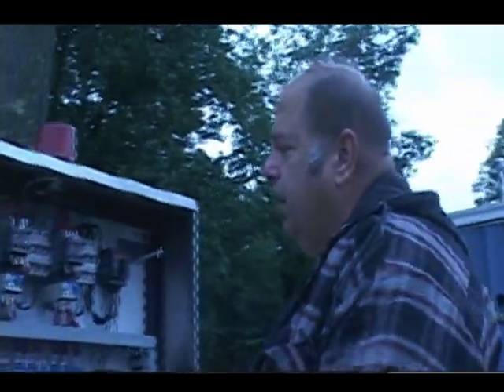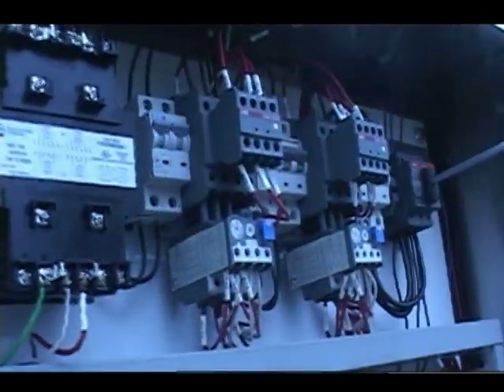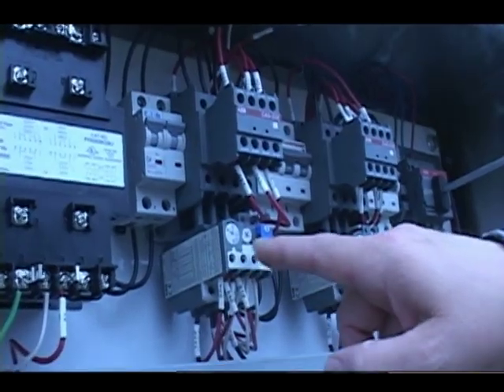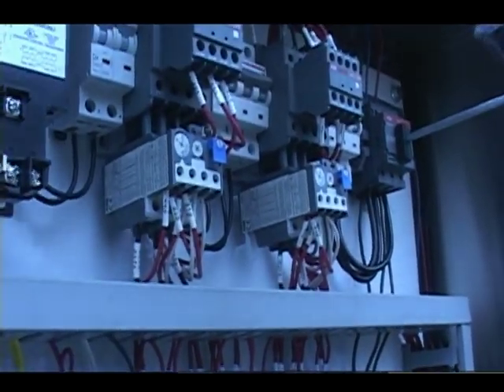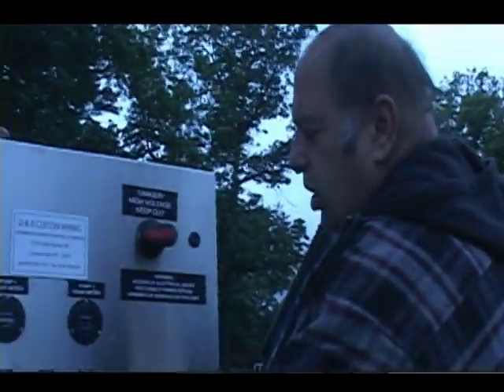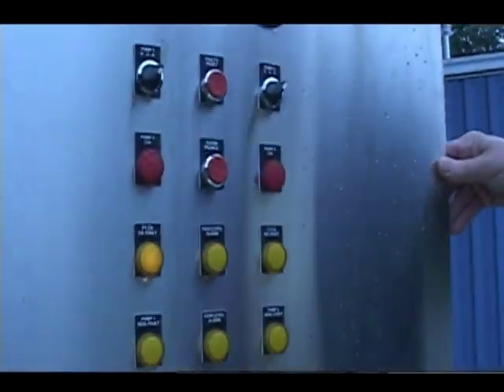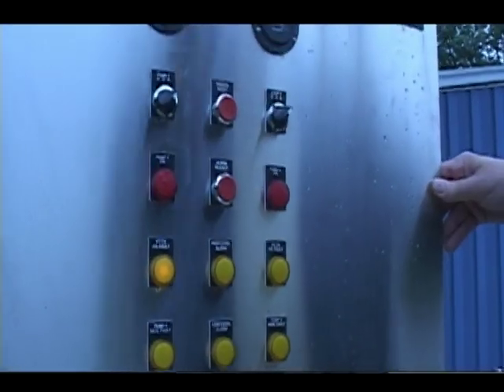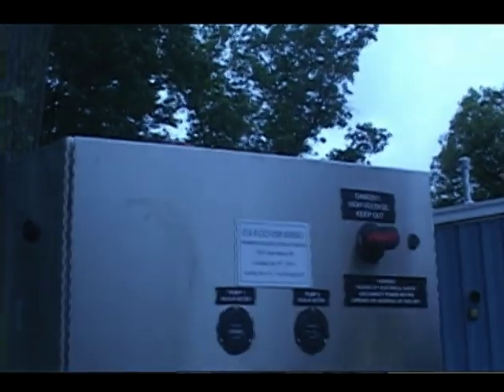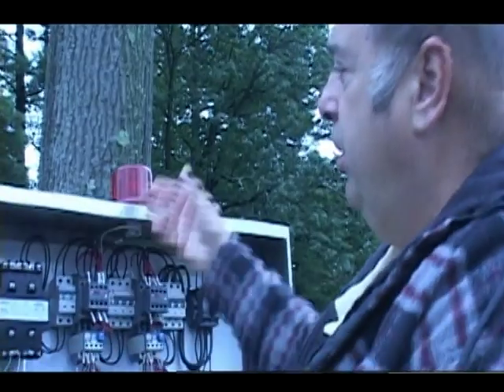Okay. One other thing I want to go over again is, and demonstrate, is if you lose an overload, you're going to get a little indicating light on the starter, the alarm light is lit, and you have the horn. Okay, now to get rid of the horn, alarm silence, the alarm light stays on and the beacon until the problem has been resolved. To resolve a starter overload problem, you have to hit the blue button, it'll reset.